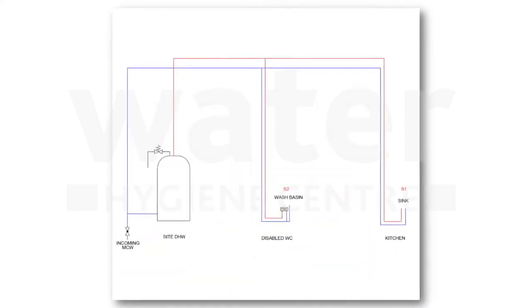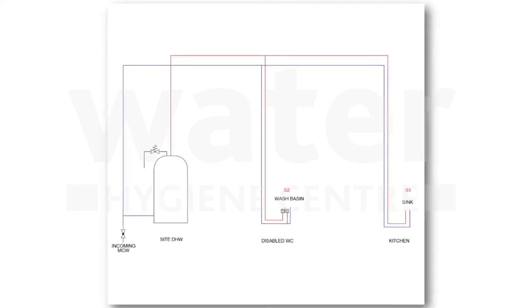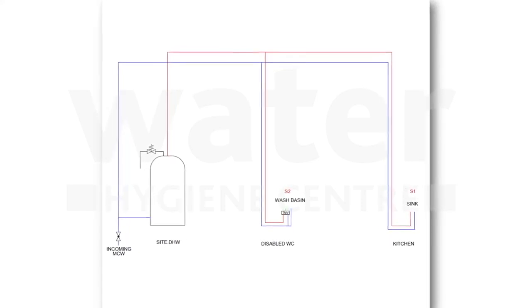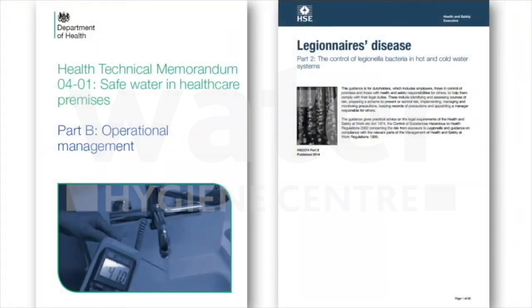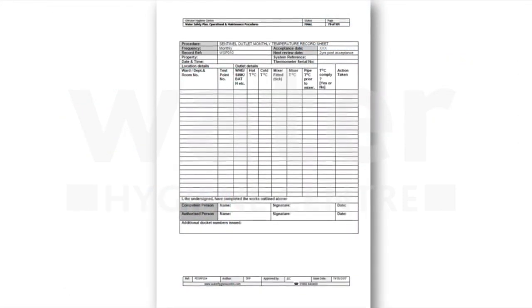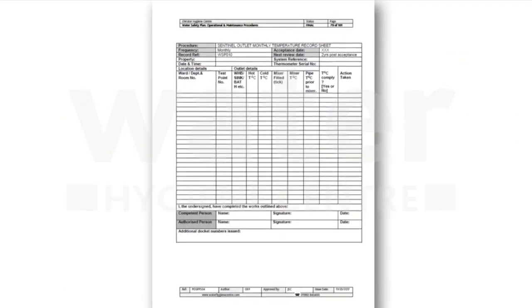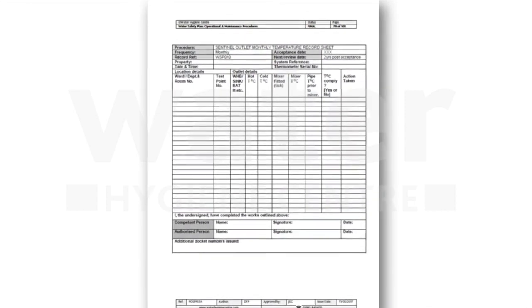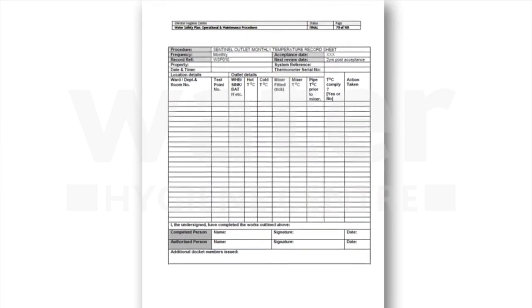If your building has a single pipe system, like the one shown here, you will need to monitor the temperatures from the outlets. Temperature parameters will be determined by the occupant's susceptibility within the building. These parameters are derived from Health Technical Memorandum 04-01 and Health and Safety Guidance 274. Accurately record your results on the monitoring form, include any comments, and ensure non-compliances are reported to the responsible person.